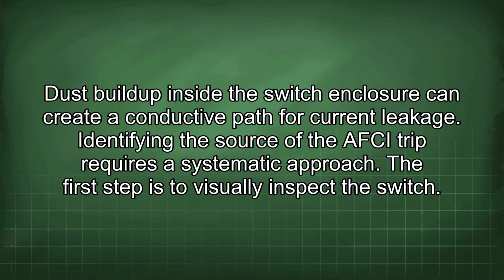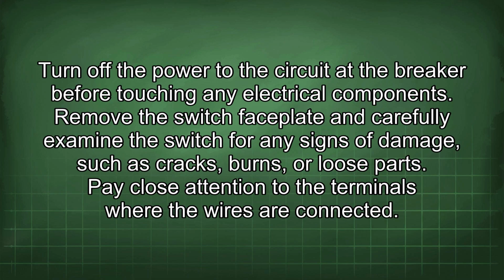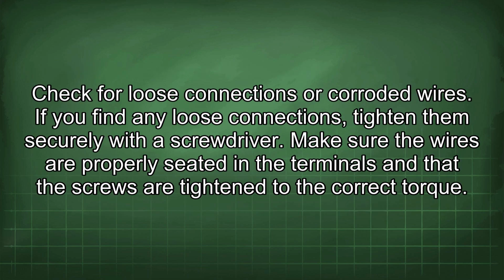Identifying the source of the AFCI trip requires a systematic approach. The first step is to visually inspect the switch. Turn off the power to the circuit at the breaker before touching any electrical components. Remove the switch faceplate and carefully examine the switch for any signs of damage, such as cracks, burns, or loose parts. Pay close attention to the terminals where the wires are connected. Check for loose connections or corroded wires. If you find any loose connections, tighten them securely with a screwdriver. Make sure the wires are properly seated in the terminals and that the screws are tightened to the correct torque.